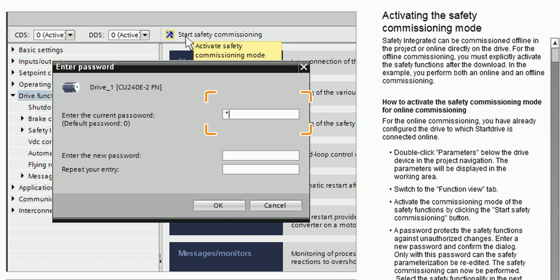A password protects the safety functions against unauthorized changes. Enter a new password and confirm the dialog. Only with this password can the safety parameterization be re-edited. The safety commissioning can now be performed. Select the safety functionality in the next step.